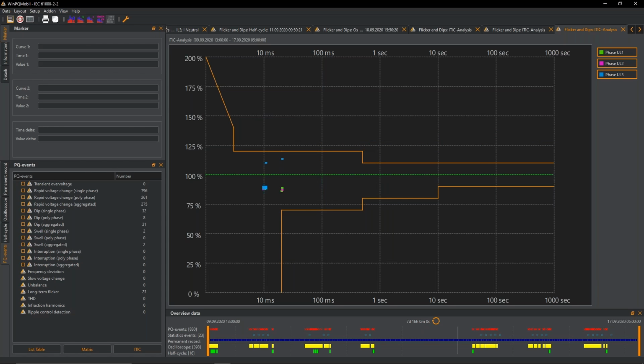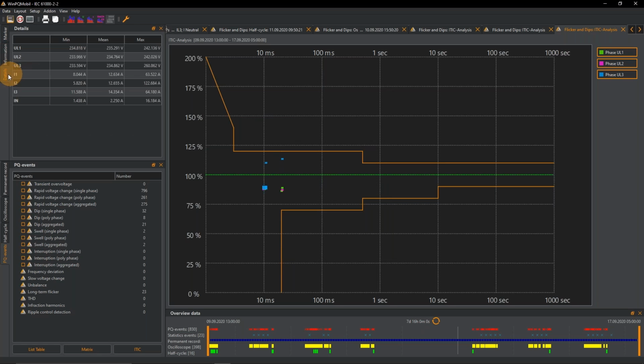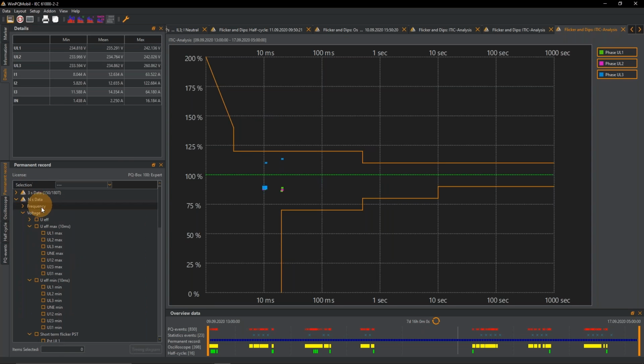So as a little explanation for the difference between the minimum, maximum currents and the 10-minute or RMS values: no data will be neglected within our PQ boxes. If you have a maximum or minimum value, you will always get the exact timestamp in a 10 millisecond raster, of course. So I will show you one quick example.